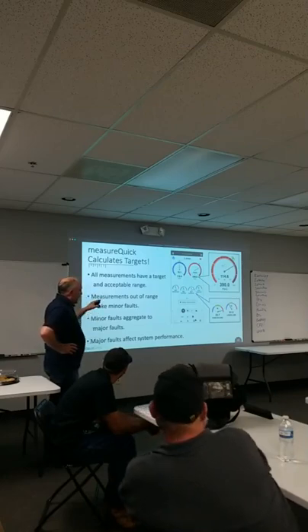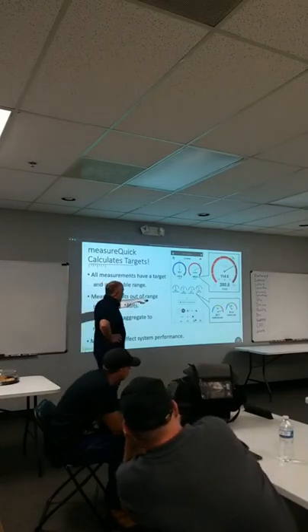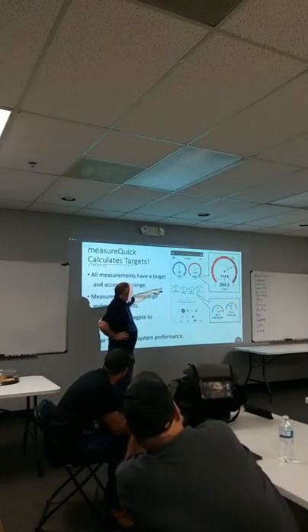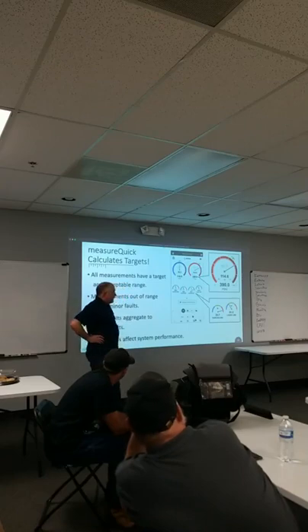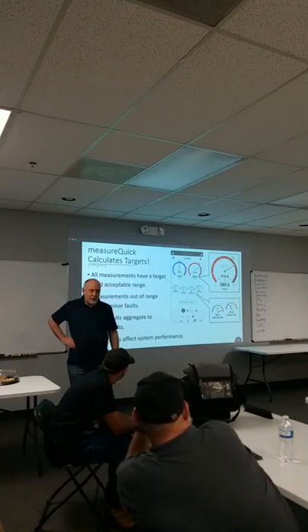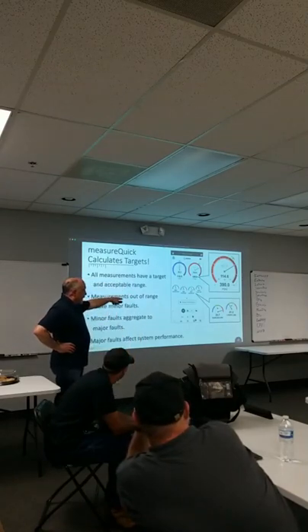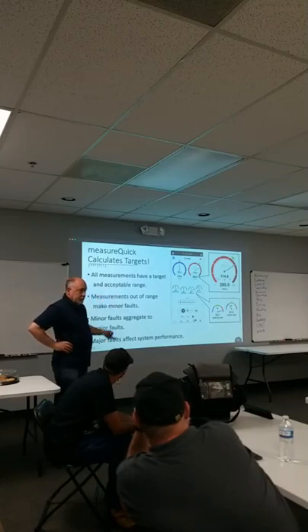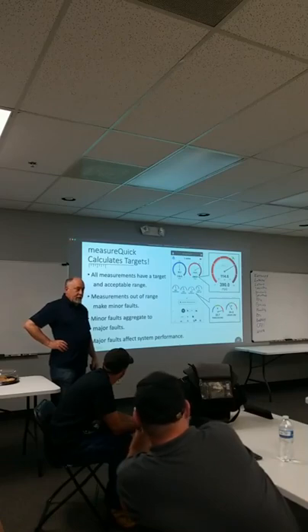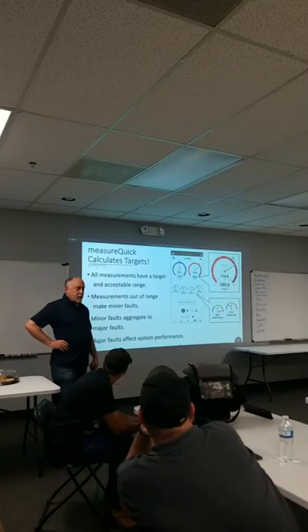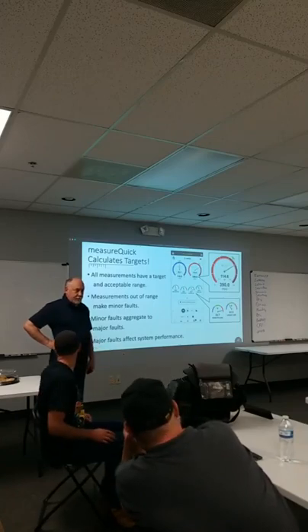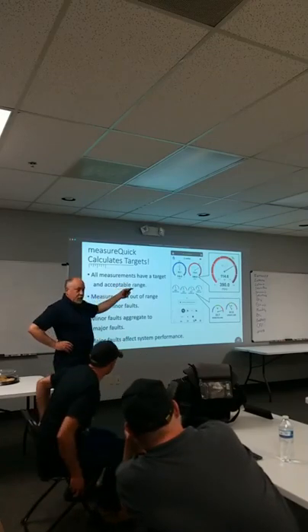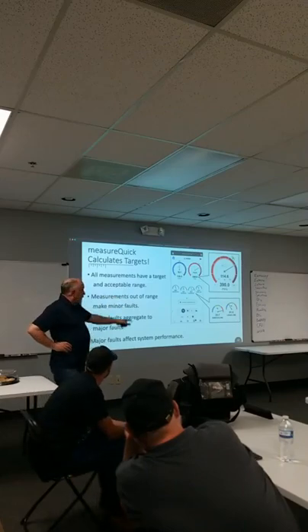So when you have a series of faults like this, in this case we have high subcooling, a low liquid line temperature, and a high head pressure on the machine. Those 3 faults, when you look at them in aggregate, tell us what? What do you think would be a good guess? If the liquid line temperature is low, what are we doing with the liquid in the condenser? Stacking it up. So we have high head pressure because we just reduced our condensing space, right? We have high subcooling, so what's that tell us?